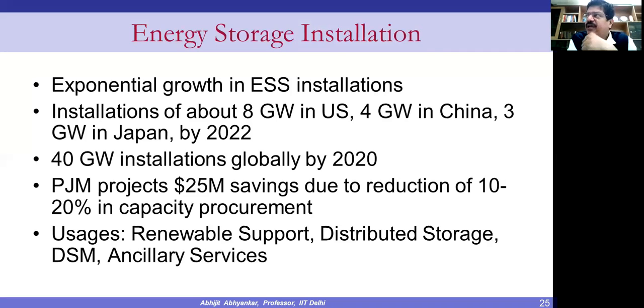Now, the PJM, that is the Pennsylvania, New Jersey, Maryland interconnection in the US, projects $25 million in savings due to a 10 to 20% reduction in capacity procurement. As I said, to compensate for the variability, the system operator needs to make a contract with the generator for buying capacity, for providing ramping up or ramping down within a certain range. This is called availability, buying capacity or making a generator available to provide the compensatory action, and the system operator is supposed to make payments for it. Instead of buying this capacity on a rental basis, if the system operator invests as part of capex in installing energy storage systems, that would be beneficial. That's the thought process in PJM and some US systems.